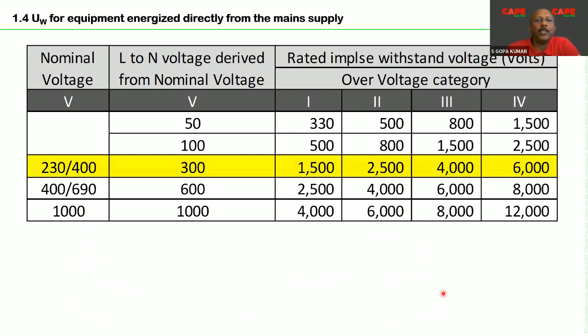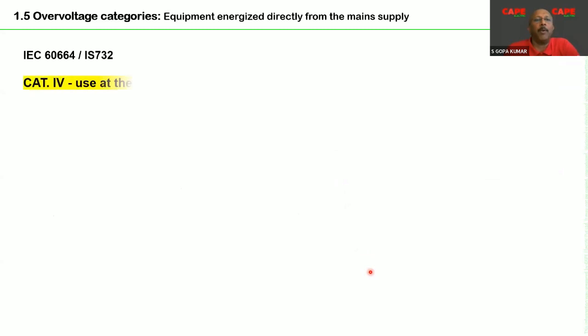And there are 4 categories of such devices, or electrical appliances, for 230/400 volt, or with a nominal voltage up to a maximum of 300 volt. They are categorized into 4 categories: category 1, 2, 3, 4. Say, for example, for 230/400 volt, category 1 is 1500, category 2 is 2500, or 2.5 kV. Don't look at the comma, I think I made a mistake. In Europe, they make a comma. So 1.5 kV, 2.5 kV, 4 kV, and 6 kV. So basically, the 4 types of voltage impulse withstanding categories are mentioned in the standard. Where they are applied is very important.